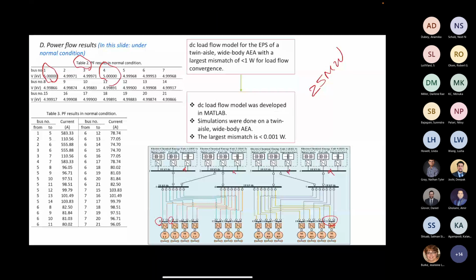About the power or current, as I said, that's what you have on the data sheet. I considered maybe 10% wiggle room, because besides the insulation on the conductor that blocks heat transfer, you also put the whole system into low pressure, which means limited convection. The results are acceptable and we could get a good normal condition. However, in the power system planning stage, you also need to consider single contingencies.